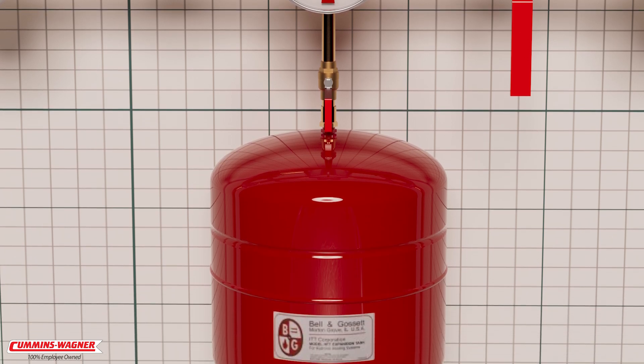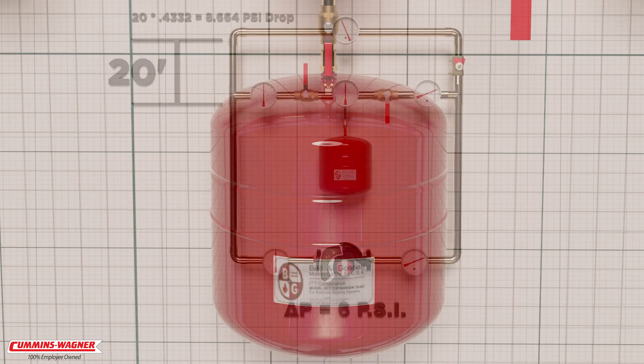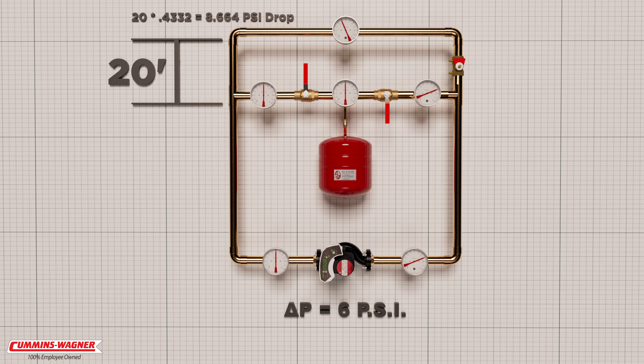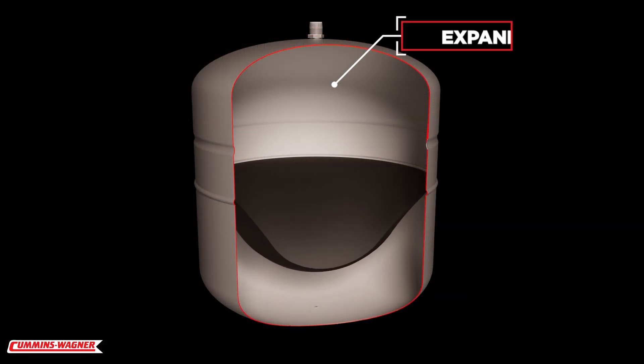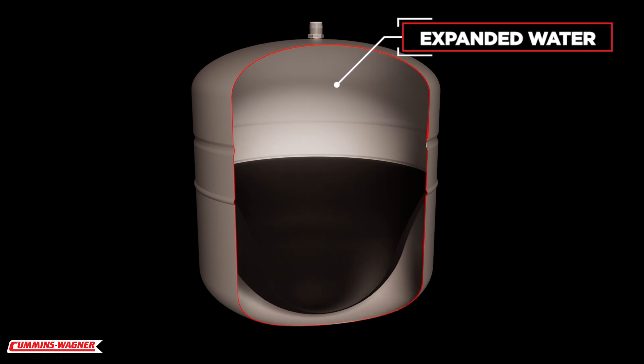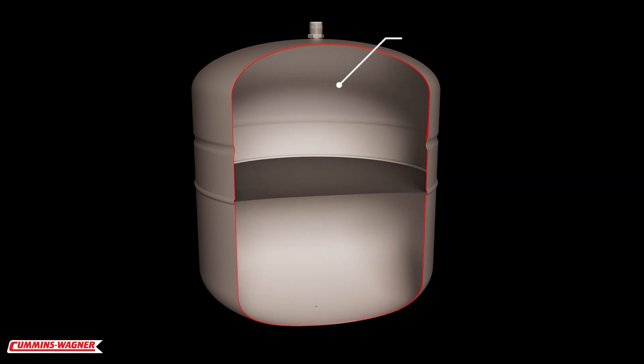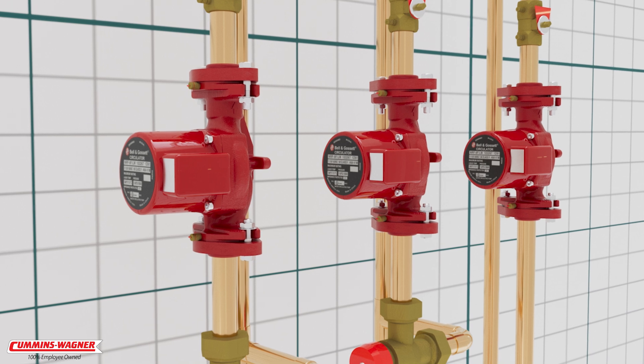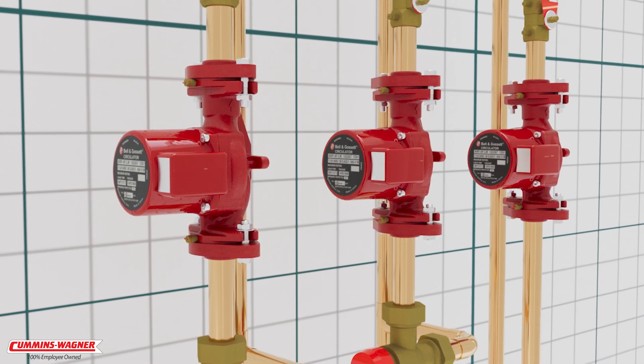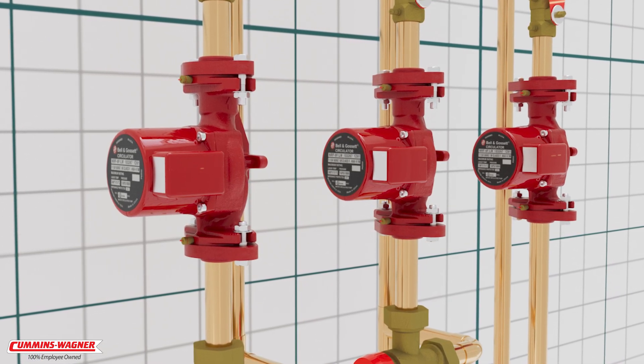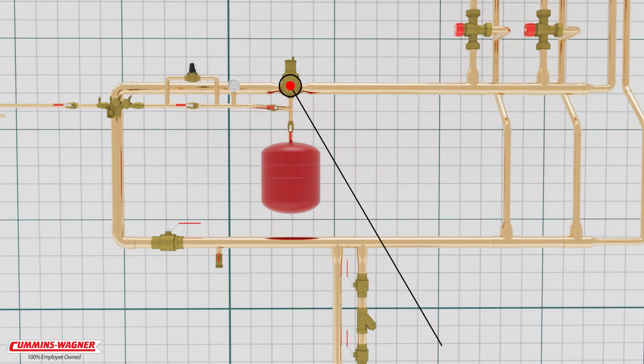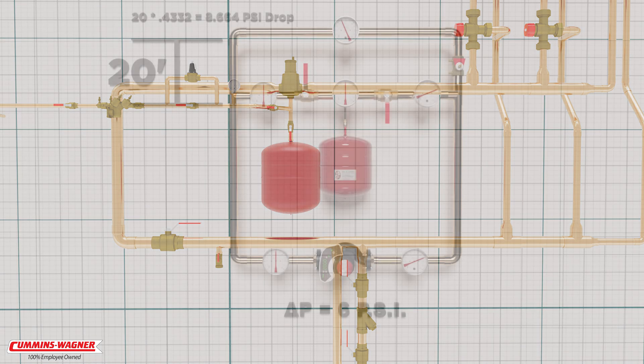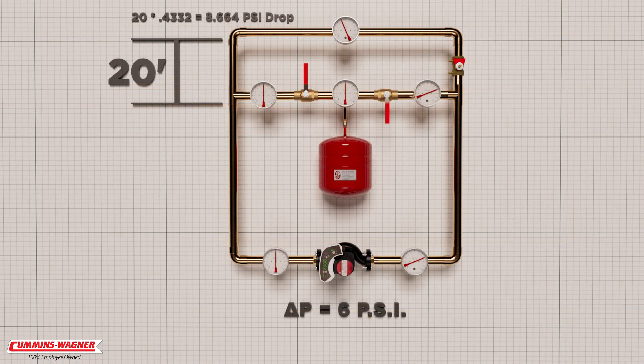But how does a circulator work if the expansion tank is isolated? The answer is very simple: the circulator has no effect on how the expansion tank functions. We use an expansion tank because fluid expands as it is heated, and the expansion tank allows a place for this expanded water to go. Since the circulator cannot increase or decrease water volume, it cannot affect the pressure at the expansion tank. This is why where we connect the expansion tank is referred to as the point of no pressure change.